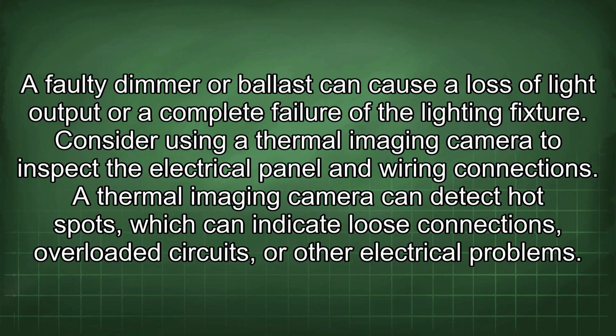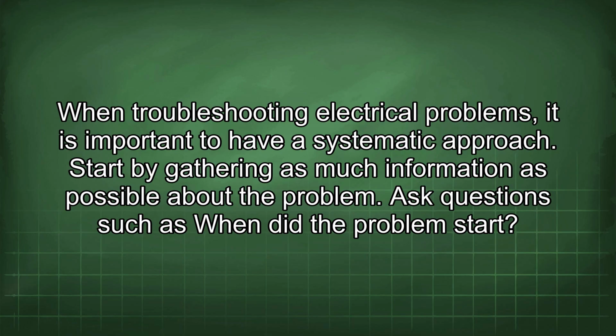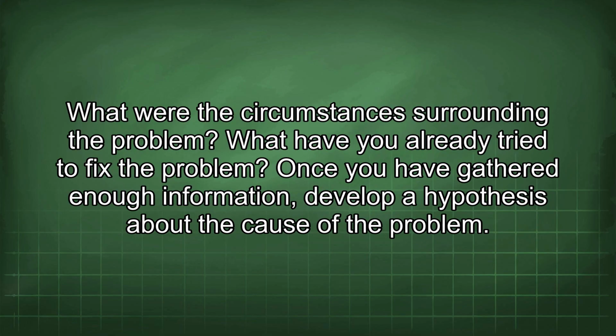Consider using a thermal imaging camera to inspect the electrical panel and wiring connections. A thermal imaging camera can detect hot spots, which can indicate loose connections, overloaded circuits, or other electrical problems. When troubleshooting electrical problems, it is important to have a systematic approach. Start by gathering as much information as possible about the problem. Ask questions such as, when did the problem start? What were the circumstances surrounding the problem? What have you already tried to fix the problem?